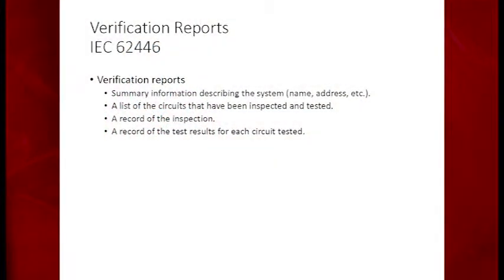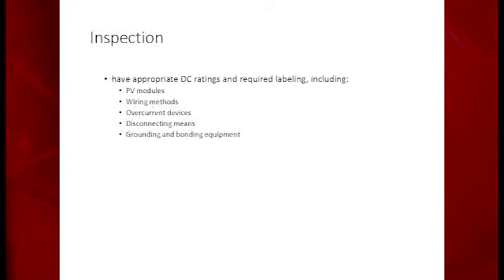Inspection is generally conducted prior to energizing the system. DC inspection verifies that all the circuits and components have been designed, specified, and installed to the applicable codes. Check all the labeling, make sure it's there, make sure everything is UL listed and compliant. Make sure you don't put things in systems that are not listed and labeled, people.